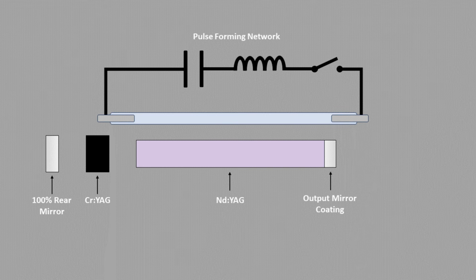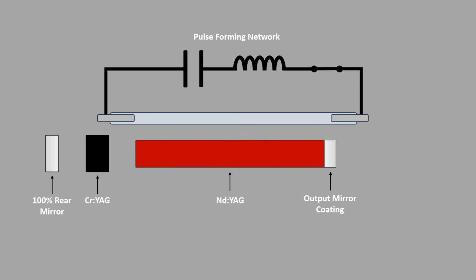The capacitor is charged up to around 1000 volts, and this stored energy is discharged into the flash lamp when the switch closes. A fraction of this optical energy pumps the neodymium atoms to a higher energy state. After a short time, some of those atoms will begin to relax back to the ground state, releasing photons, but the system cannot efficiently laser as the Q switch is currently almost opaque.